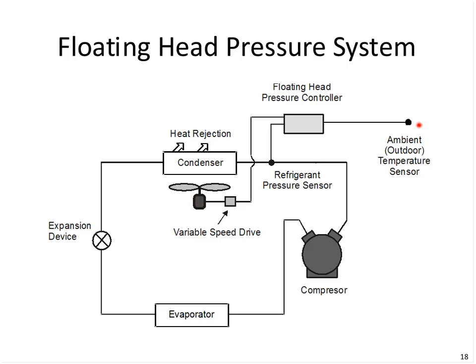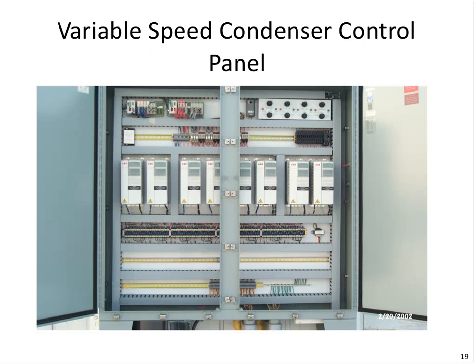We might say, why not have this control system? Why not have floating head pressure control? And sometimes this is the reason. This is a variable speed condenser control panel. You can see the variable frequency drives here. These are for the condenser fans. There's other controls, a microprocessor controller, and of course this takes extra care. Some feel that these added controls are more complex than they want to deal with. However, we're seeing savings in the neighborhood of 15 or 20% on an annual basis.